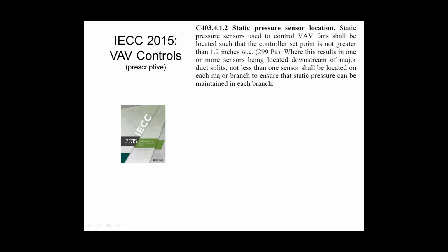But we don't know what that is typically on the control side, so we just put it two-thirds down and kind of said, great. Now the code is such that you have to locate the duct static pressure sensor somewhere that is 1.2 inches or lower of a set point, right? So if I have to run the system at 1.5 inches in order to get airflow to make the balancer happy, guess what? I've got to put the static pressure sensor further downstream than that, because that was only 1.5. I can keep moving down the duct till I have less static pressure that gets me what I need for CFM. So that's something to keep in mind.